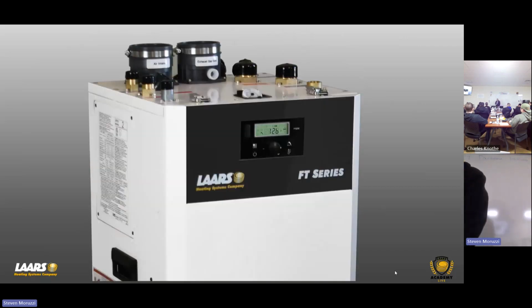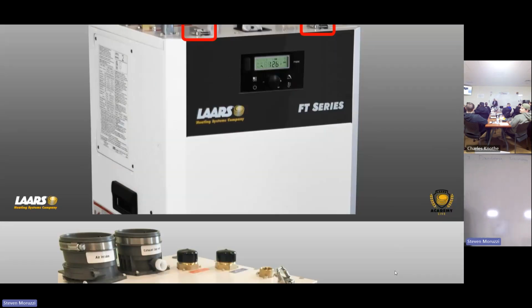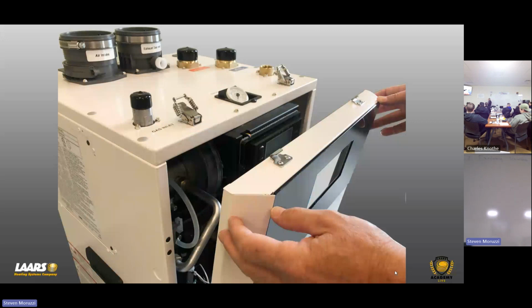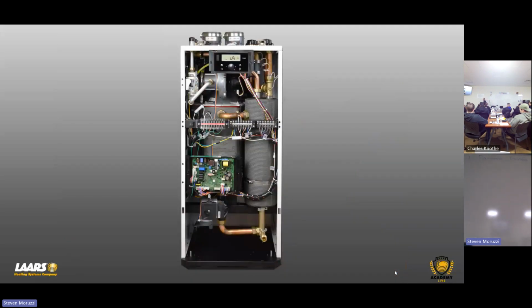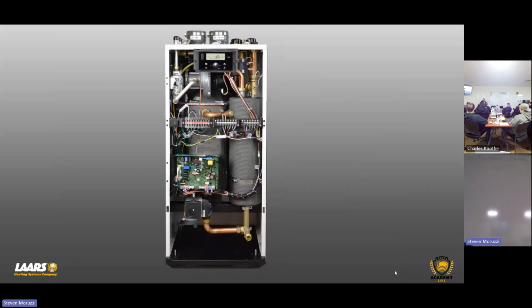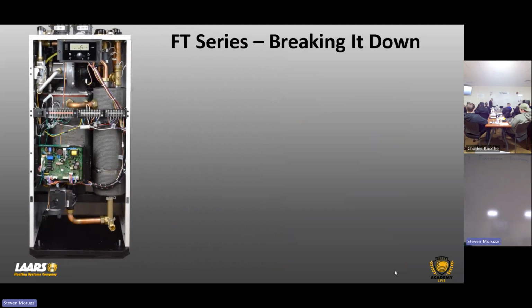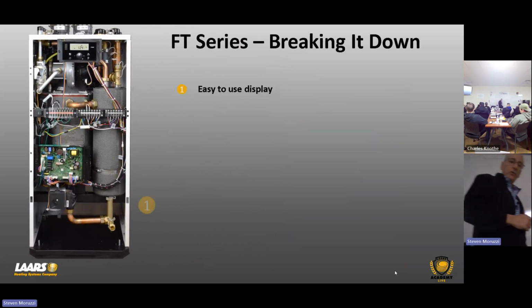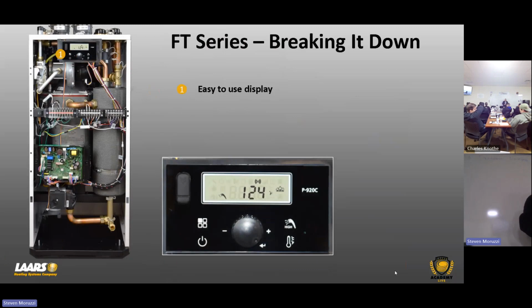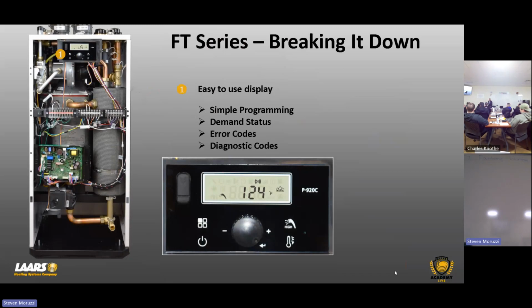So we give you 3 large service access panels. There are 2 latches right on the top. And you lift those latches and take that panel right out of position, and there it is, okay? So components are all going to be the same. Easy to use display right there in the top. And again, we have videos on all of this, how to get into setup modes and diagnostic modes and programming and outdoor reset, etc. So simple programming, demand status, and error codes, all right?